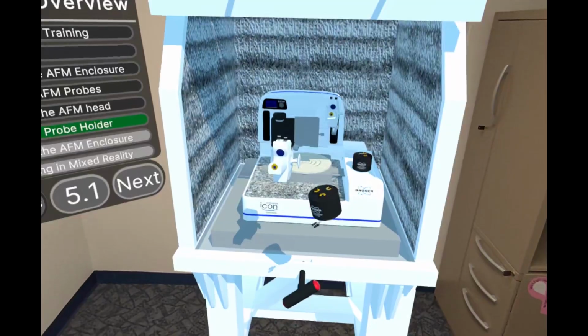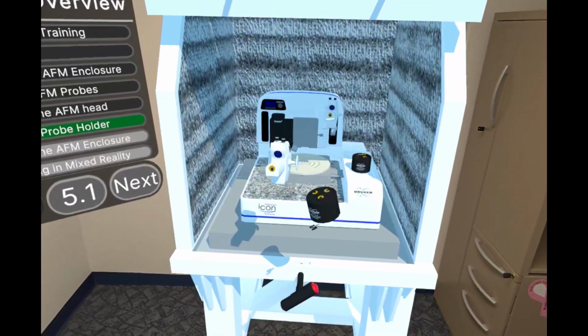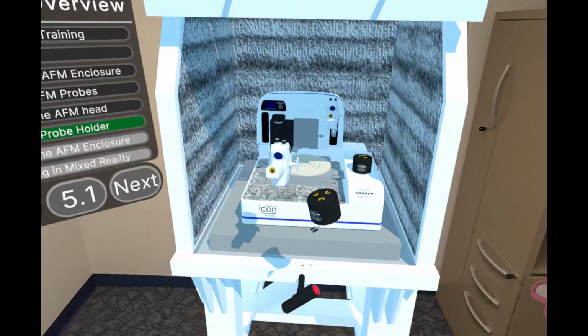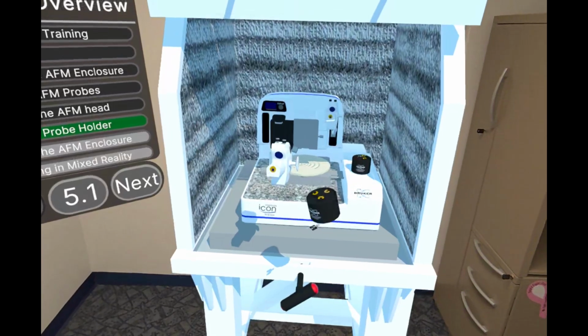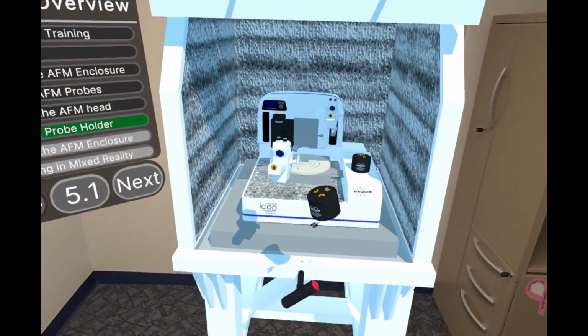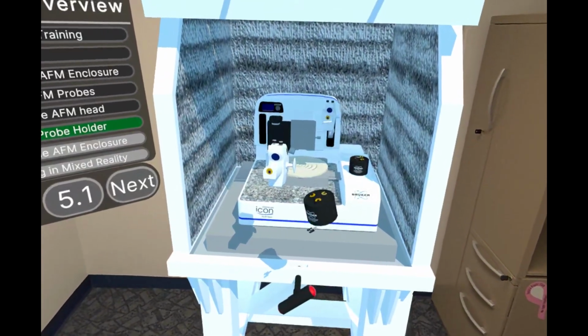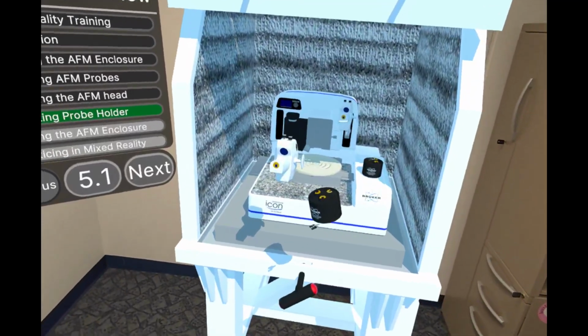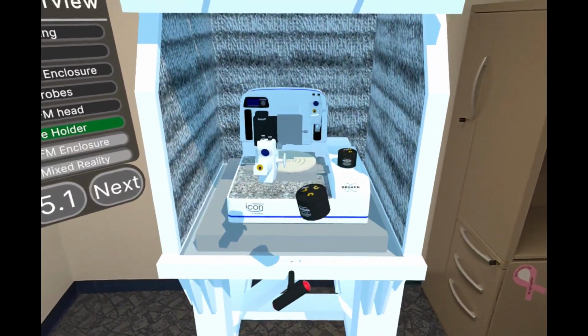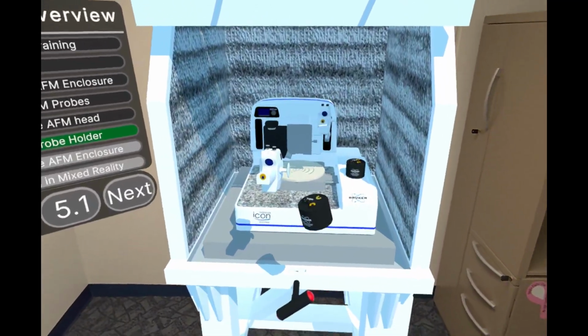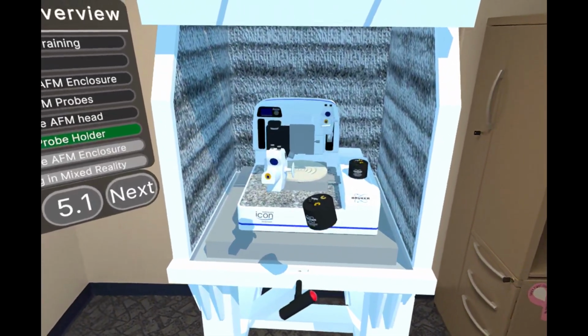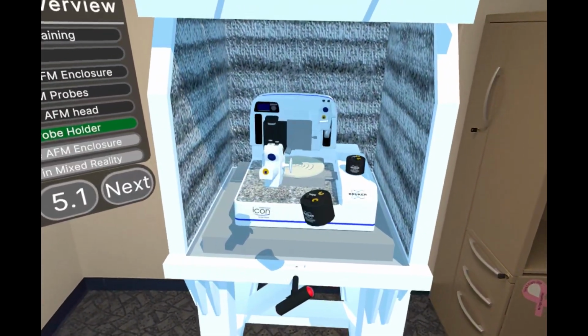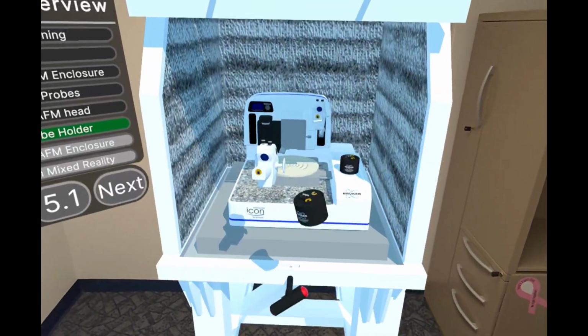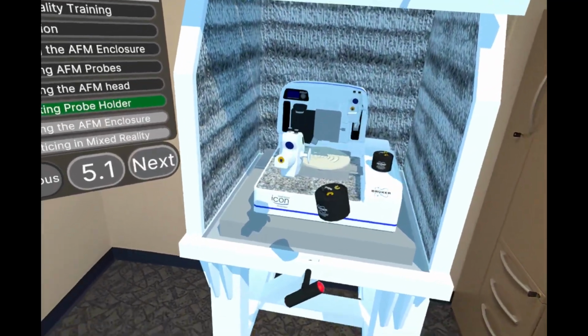The probe holder pins must match the AFM head pin alignment. Notice the pins on each side of the probe holder are not the same distance apart. To make mounting easier, rotate the probe station so that the probe holder lines up with the pin orientation on the AFM head. Use a crab claw grip with the very tips of your fingers to avoid touching the cantilever and having your fingers get in the way when trying to mount on the AFM head.